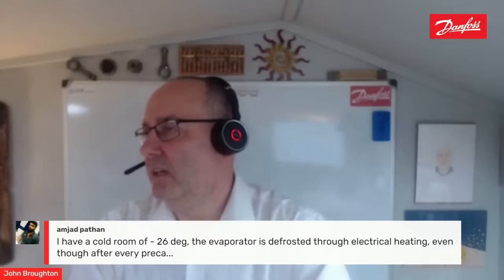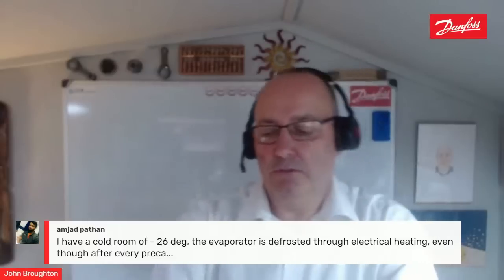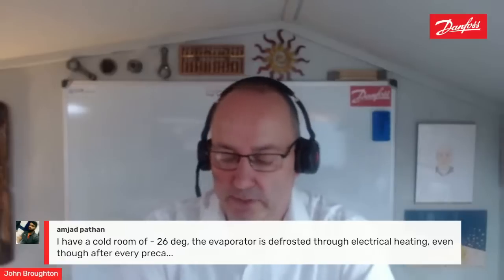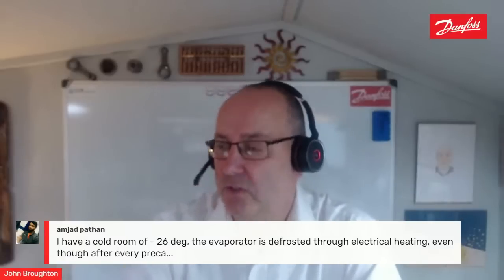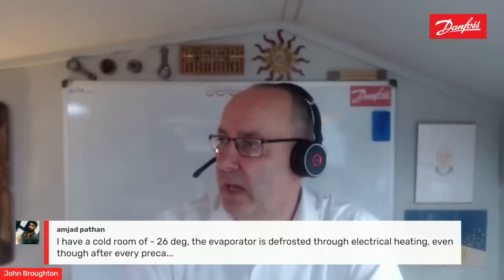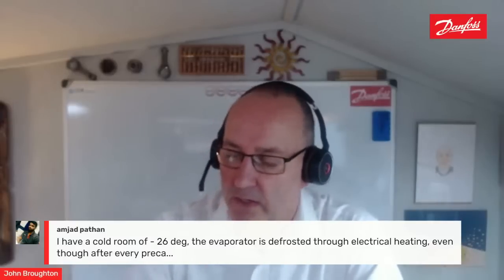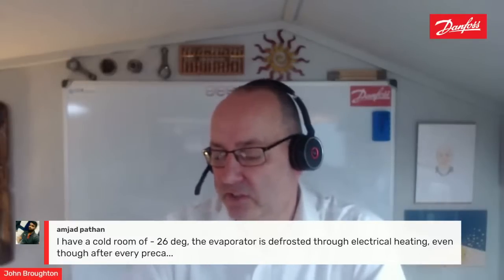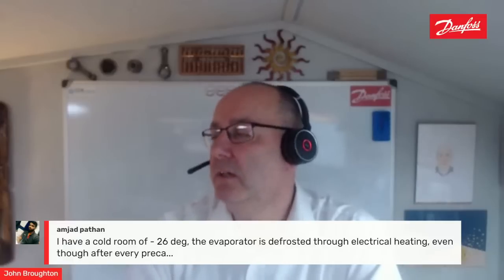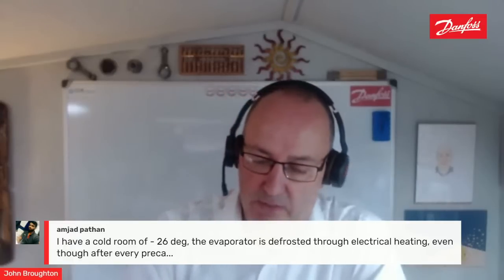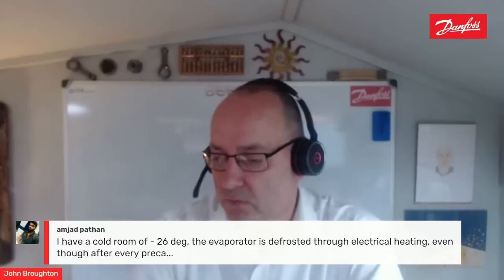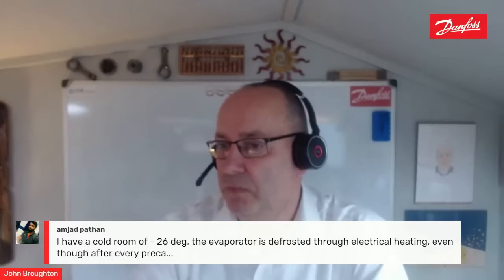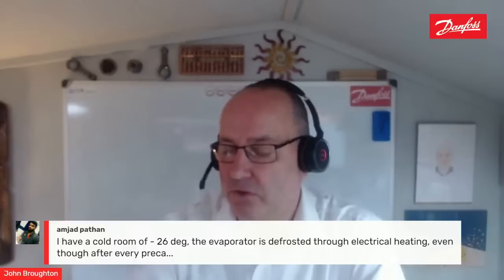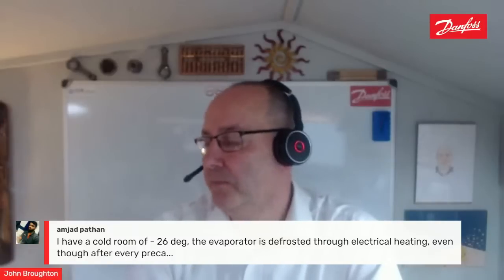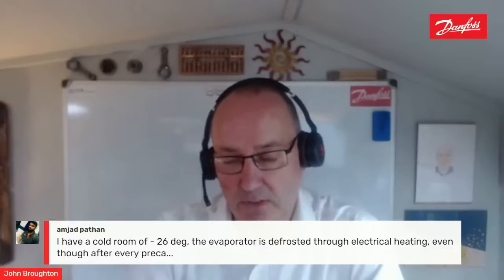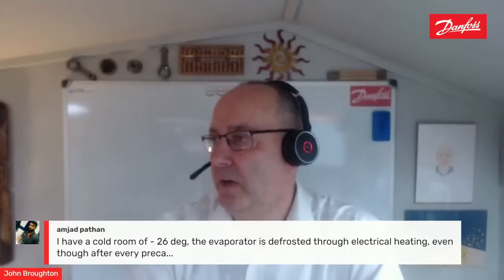That's a good one. The function of a defrost heater, as we know, is to melt the frost, the ice that's built up in the evaporator. I would ask a question: where are they actually failing? Are they blowing? Is it a dead short, or does the heater just stop working? What I try to do is, when we have a defrost cycle, one of the biggest challenges is the location of the defrost heaters, the location of the defrost termination stat, the drip down time and the fan delay on the evaporator.